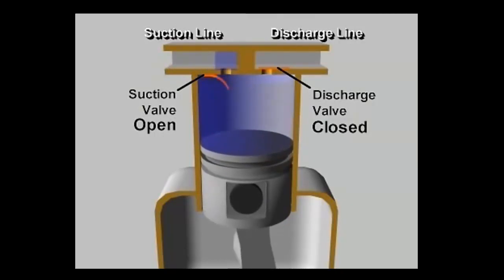The piston continues down and pulls in more vapor until the cylinder is filled with low pressure vapor at the bottom of its stroke. Once past bottom dead center, the piston begins its upward stroke. The suction valve closes.